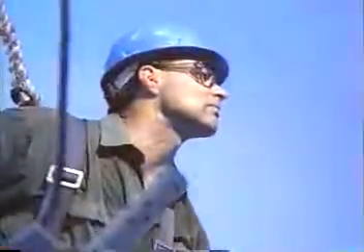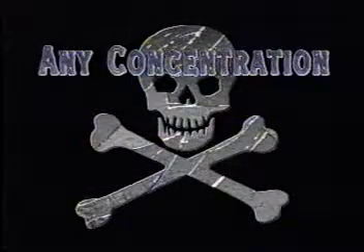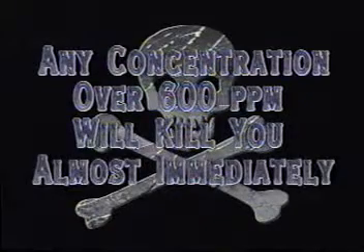In addition to these effects, from 100 to 300 parts per million, you'll become drowsy. Eye and throat irritation is more severe, and possibly you'll experience pulmonary edema, which is respiratory difficulty due to fluid in the lungs. Up to 600 parts per million, you'll lose your sense of reasoning and balance and eventually become unconscious. Although these effects may vary from person to person and the length of exposure, any concentration over 600 parts per million will kill you almost immediately.